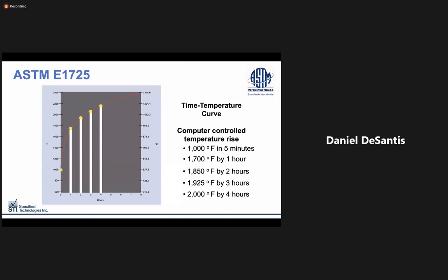During this test, thermal sensors are placed inside of an enclosure on a bare copper conduit. In order to pass this standard, the average temperature rise across all sensors may not exceed 325 degrees above ambient, or about 400 degrees total. When you use an endothermic wrap tested to ASTM E1725, you're using a product that's been third-party tested with these strict parameters by an independent lab.